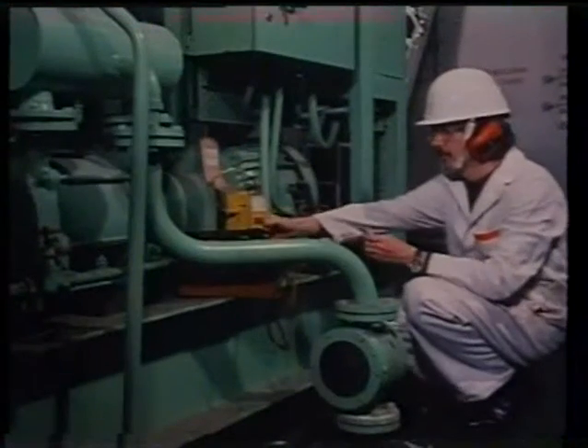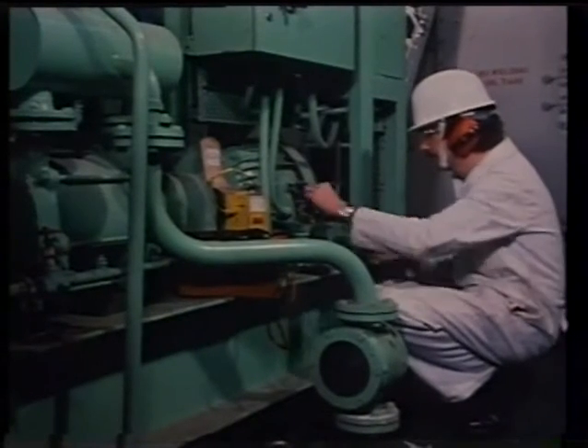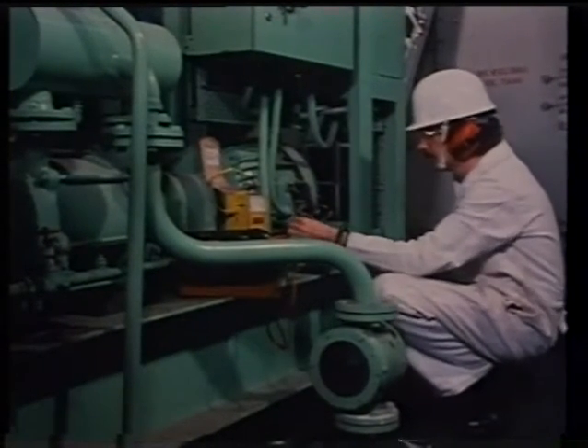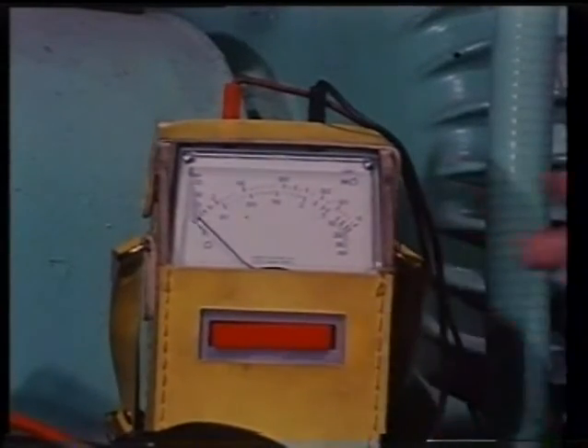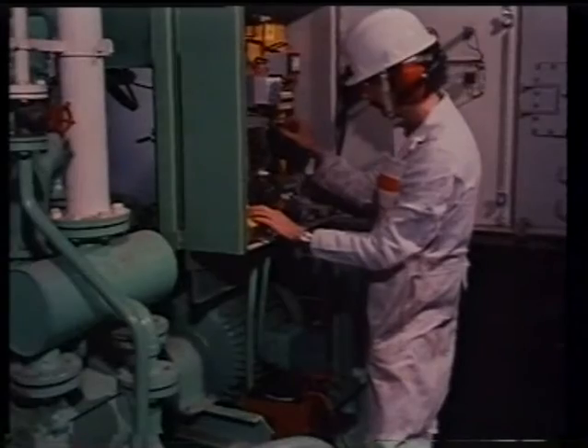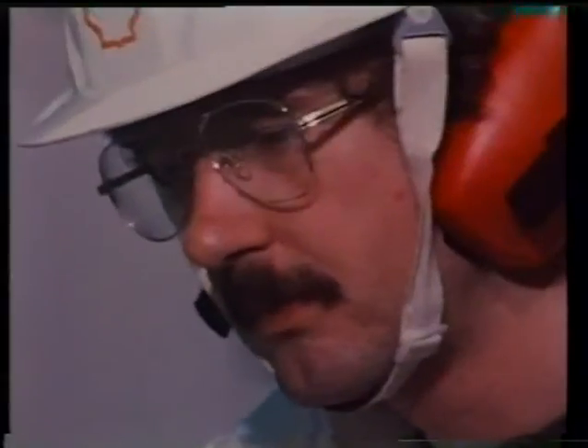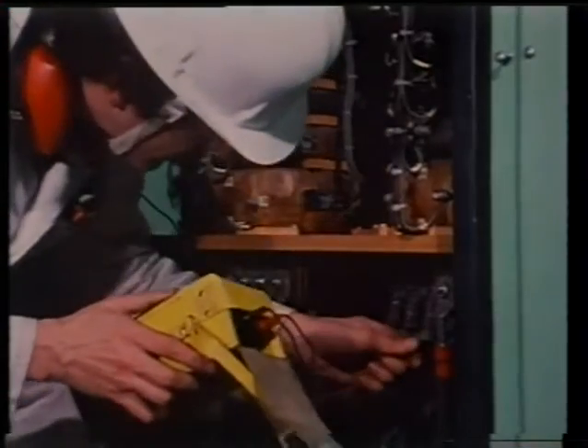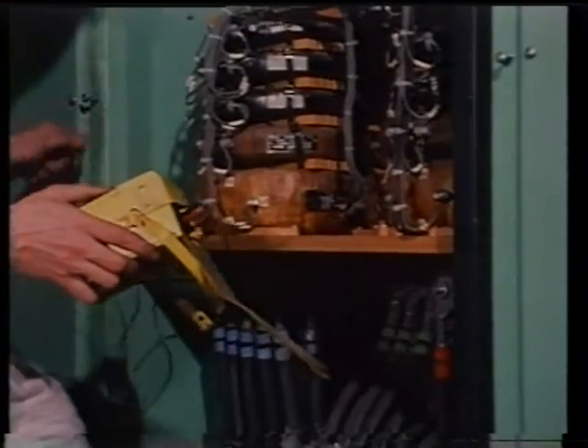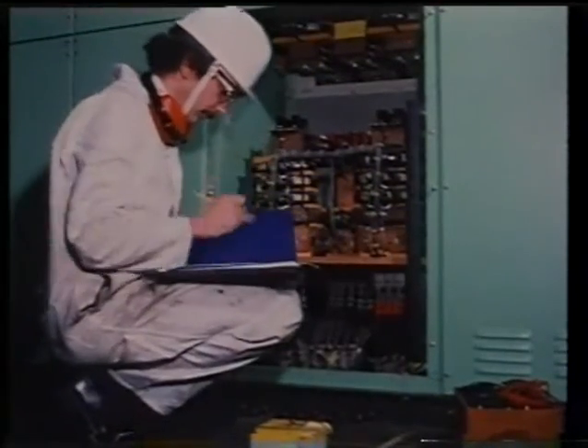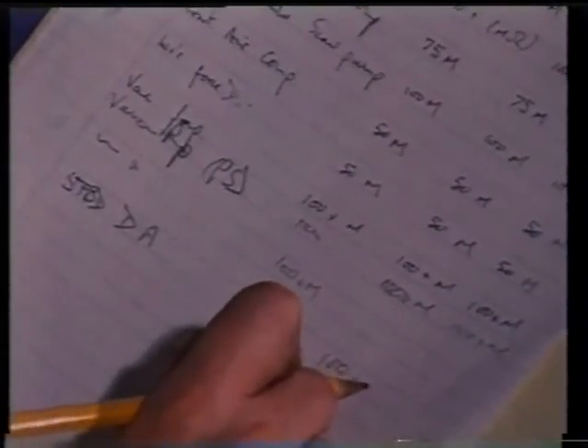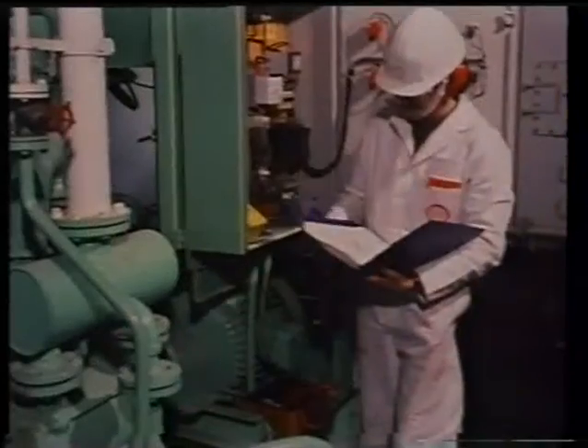The ship's electrical equipment is inspected and tested during the complete engine survey, which is carried out every 4 years. The electrical survey guidance given in this programme is based on the periodical survey regulations of a classification society. First, prepare a complete list of all insulation resistance readings for AC generators, motor, power and light circuits and main feeder cables, with special attention to cables in hazardous areas. When you take insulation resistance readings of AC generator windings, this should be done when the AC generator is still hot after running on load. A reading of 1 megohm is an acceptable value for a 440 volt AC generator winding. For the lower voltage rotor winding, this can be 0.5 megohm.